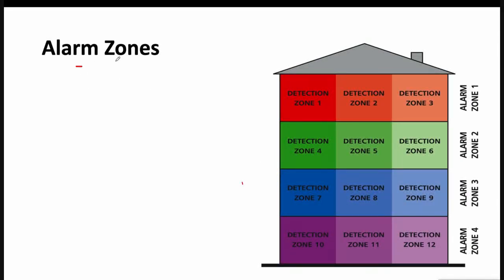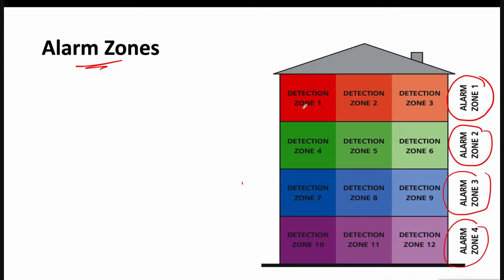For alarm zones, it is recommended to divide the building into zones where each entire floor is one alarm zone. A floor may have many detection zones, but it will have only one alarm zone.